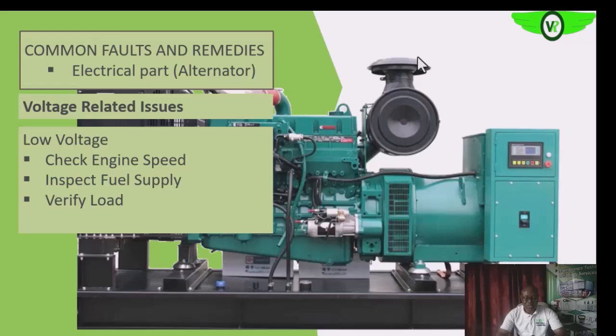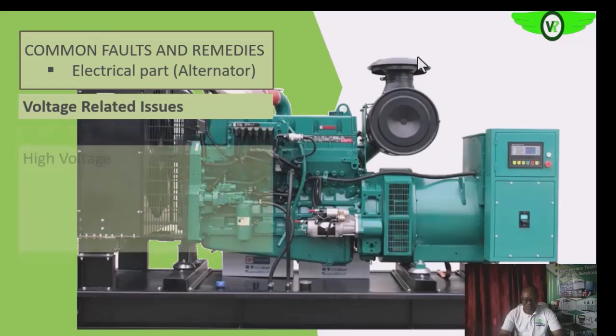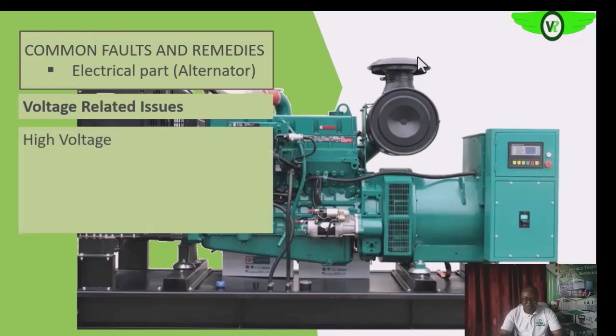Overloading too can cause low voltage — if there are more loads than the system is designed for, it will drag the engine and the voltage will drop. Check that the load is normal. The excitation system can also cause low voltage: if the voltage from the AVR is low, the magnetic field at the exciter field will be low, the exciter armature output will be low, what is rectified will be low, and thus what is induced into the main armature will also be low.